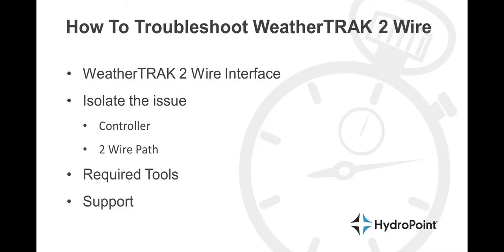In a nutshell, that's how to troubleshoot WeatherTRAK 2-Wire. First, isolate the issue — make sure it's a problem with the 2-Wire path and not a WeatherTRAK issue. Then isolate the issue on the hardware by separating the controller from the 2-Wire path. Then use the required tools to troubleshoot the 2-Wire path and find the short in the field.